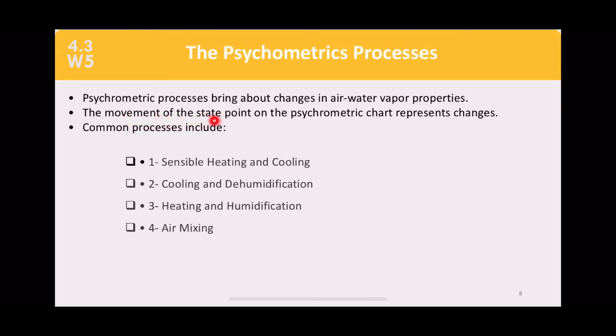Psychrometric chart processes represent the changes in air and water vapor properties, which change temperature and comfort inside a room. The movement of state points represents these changes. You need to find State 1 and State 2 to see the heating or cooling process. There are four common processes: sensible heating and cooling, cooling and dehumidification, heating and humidification, and air mixing.